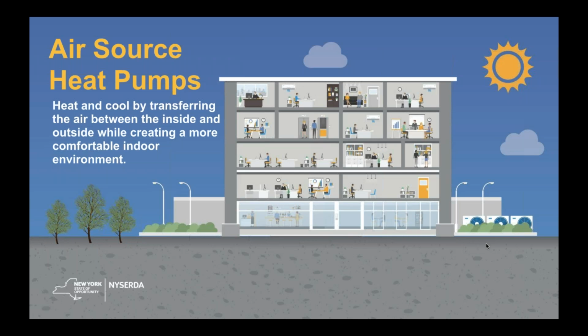Air source heat pumps can deliver 1.5 to 3 times more heat energy to a building than the electrical energy it consumes. This is possible because a heat pump moves heat around rather than converting it from a fuel like combustion heating systems do. Air source heat pumps have been used for many years in nearly all parts of the United States, but until recently they have not been used in areas that experience extended periods of sub-freezing temperatures. However, in recent years, air source heat pump technology has advanced so that now it's a strong alternative to conventional heating in colder regions like in New York State.